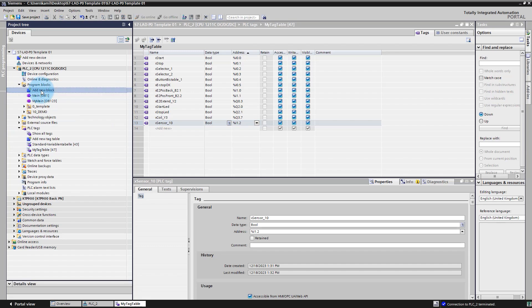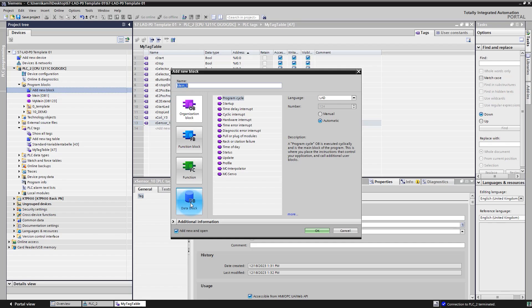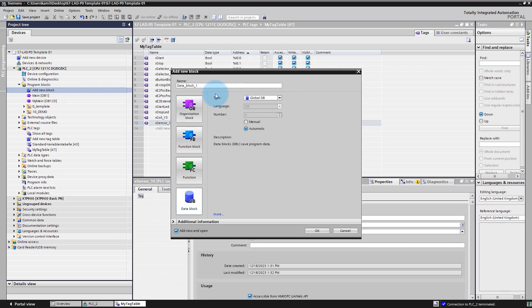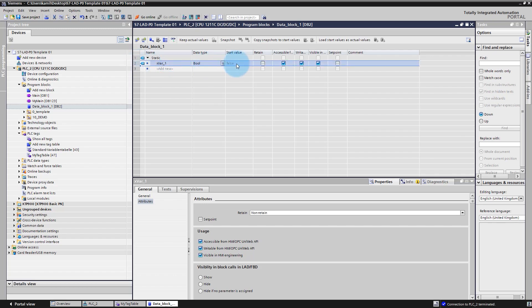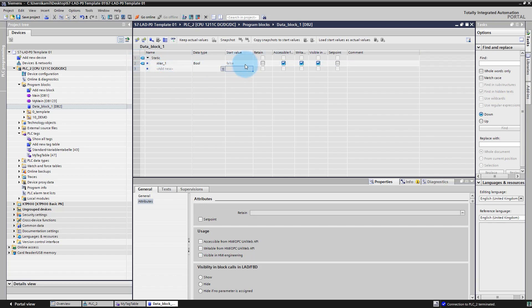Click Add New Block and here you can define a data block. This is the last type of variable declaration you can do in your project. Click OK. A new data block appeared in your project. Here you can define a variable, for example X_Variable1. This is a boolean type variable and you can assign a start value. As you can see, there is no address for this variable — it is declared inside the data block and can be used in your code.